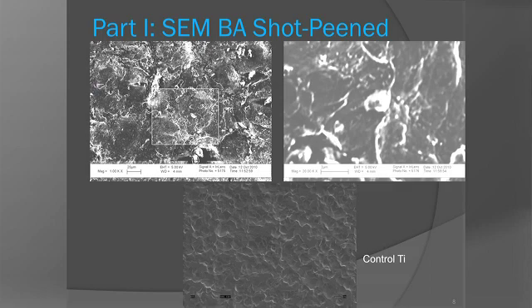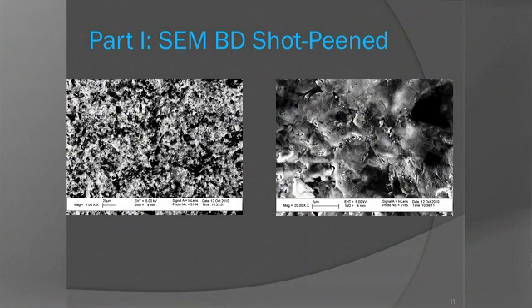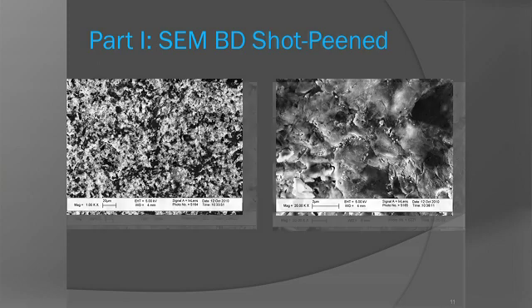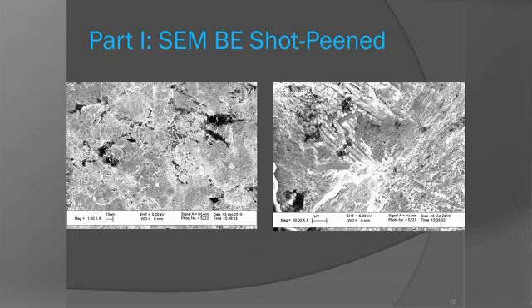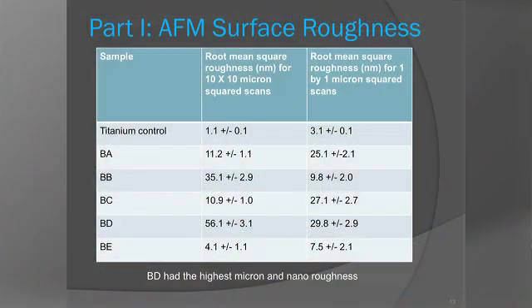Here are some SEM pictures. The BA sample is only the titanium alloy. The BD sample, which also increased roughness, was a combination of everything discussed so far — the most aggressive change of surface roughness. It was exposed to the stainless steel cut wire, then microbeaded, followed by type 2 anodization. BE was a different type of microbead process using a ceramic rather than a metallic microbead, which also demonstrated increased roughness. We used an atomic force microscope to quantify the roughness change, and everything compared to the titanium control was more rough. The BD material, using shot peening combined with type 2 anodization, showed the greatest roughness.